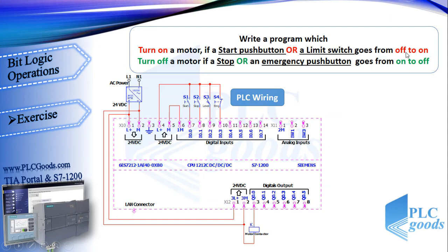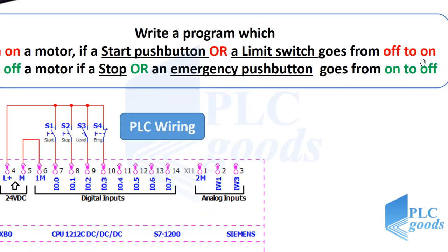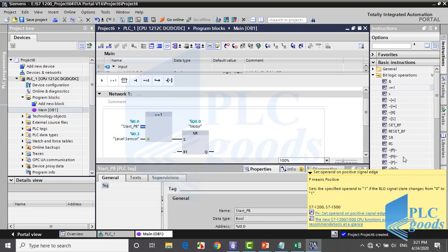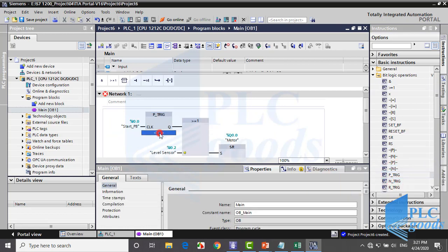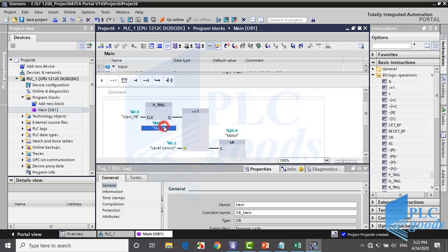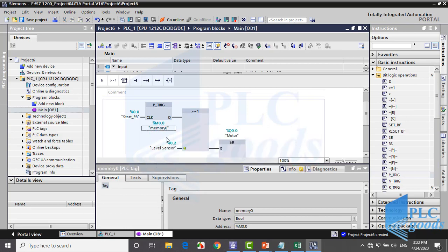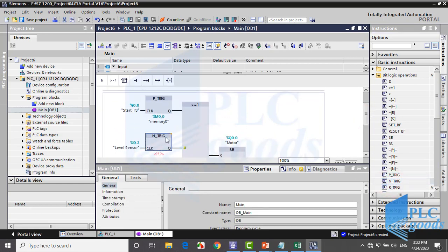The motor will turn on based on a positive edge at the PLC inputs. So I click here and add this instruction. A bit memory address must be written here — pay attention, you must not use this address again. This must be sensitive to the positive edge, not negative, so I click here to replace it with its similar instruction.